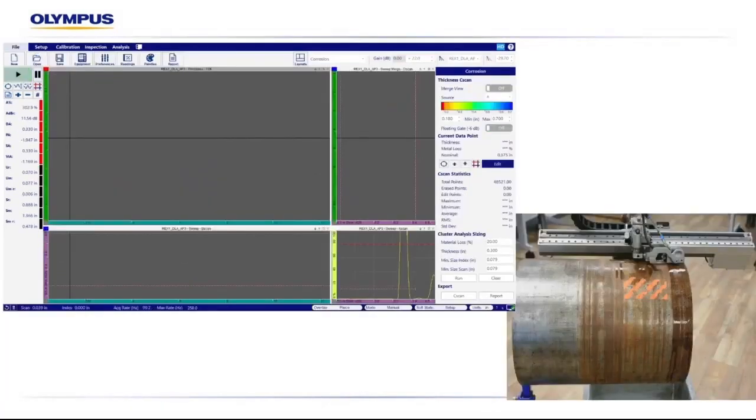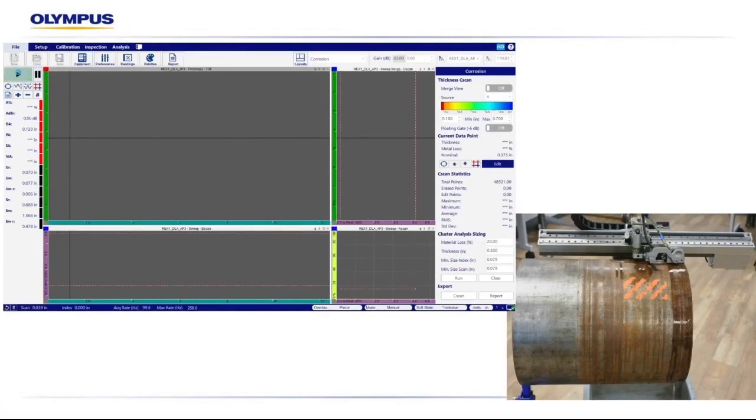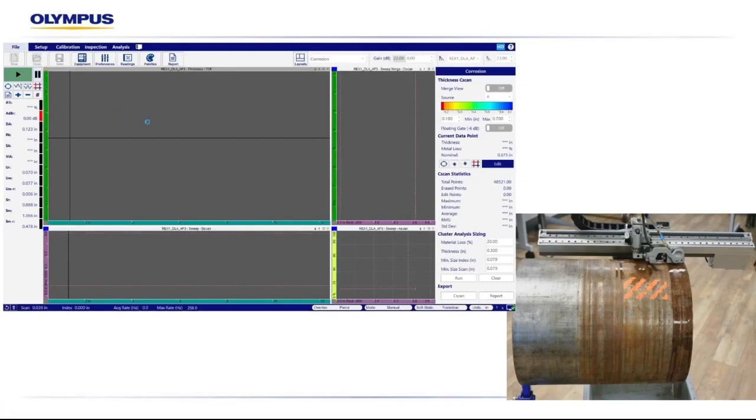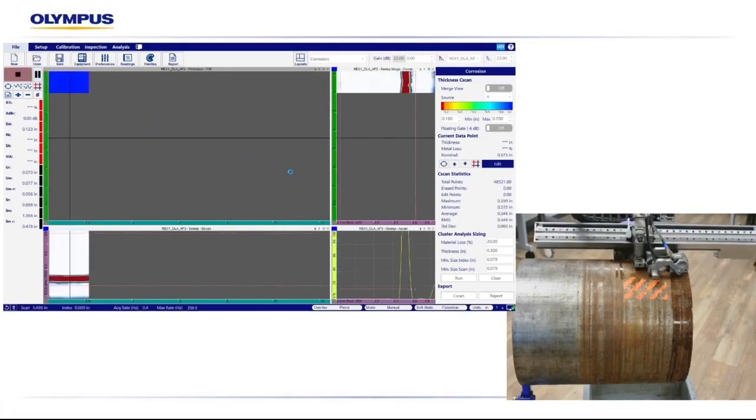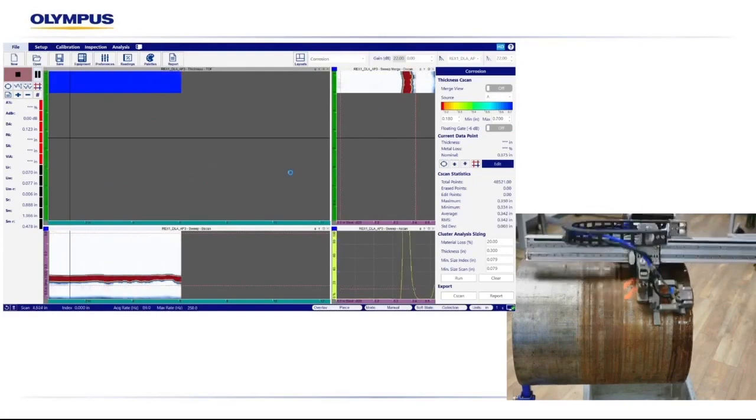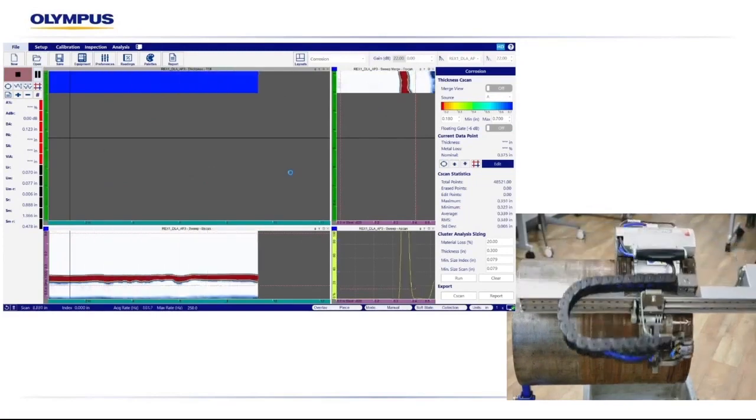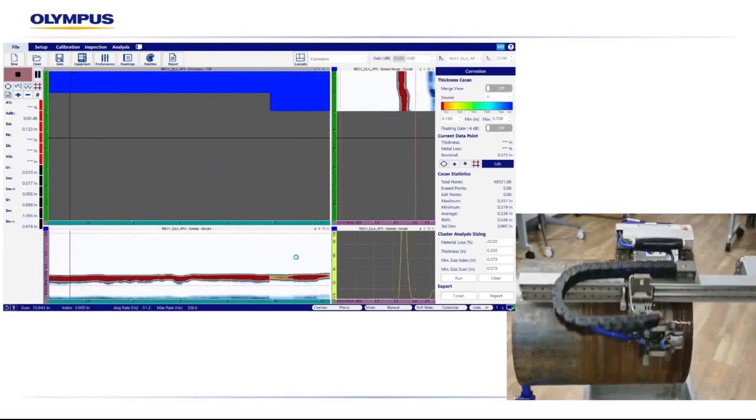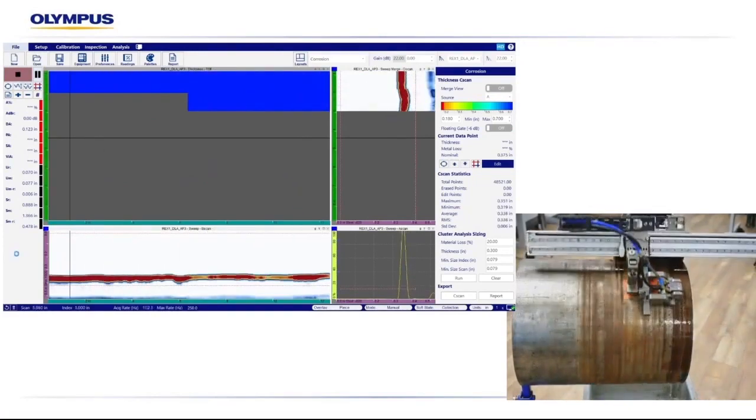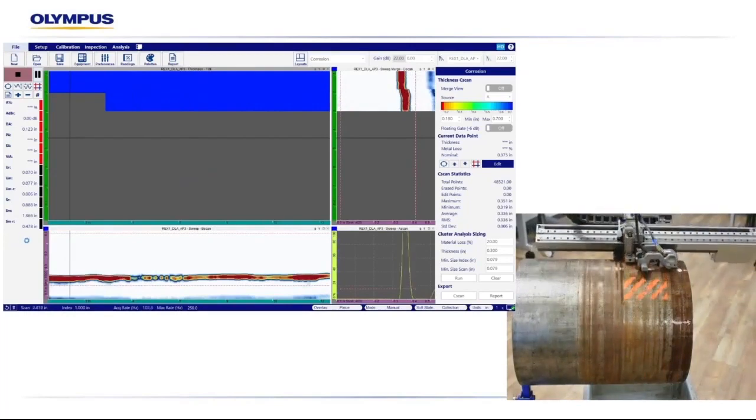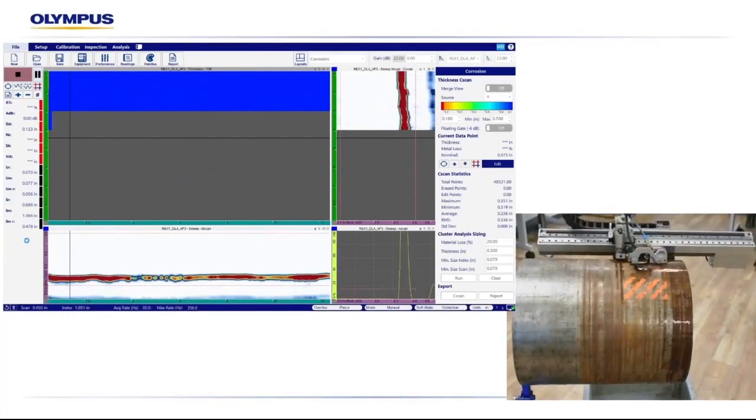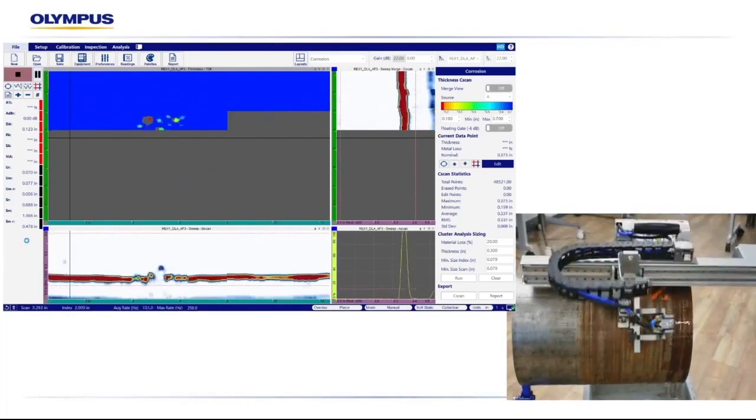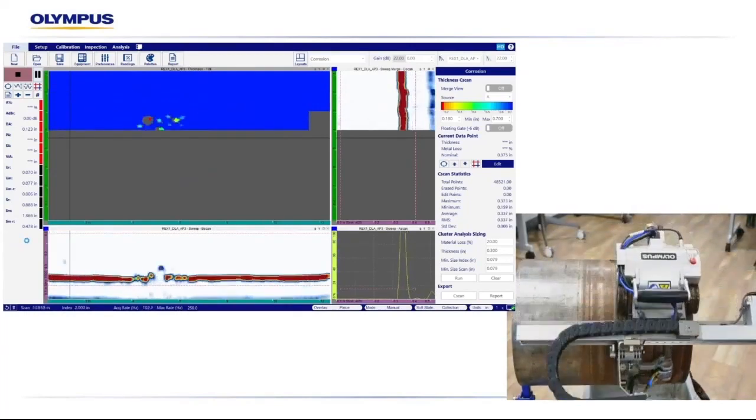Here I'm going to show you the data acquisition process for a zero-degree corrosion inspection. We'll select the play button to start our inspection, and then we'll start the scan on our Olympus MapRover scanner. In this demonstration, we're utilizing the REX1 dual linear array corrosion probe to perform a raster scan on our mock-up pipe with simulated internal wall loss.